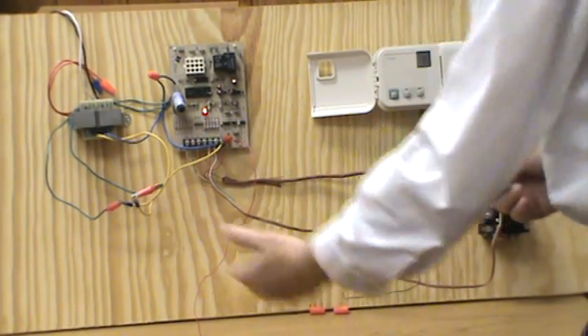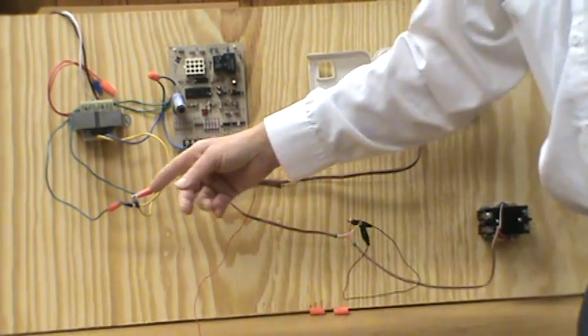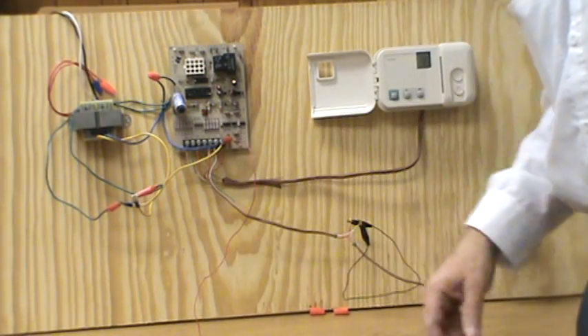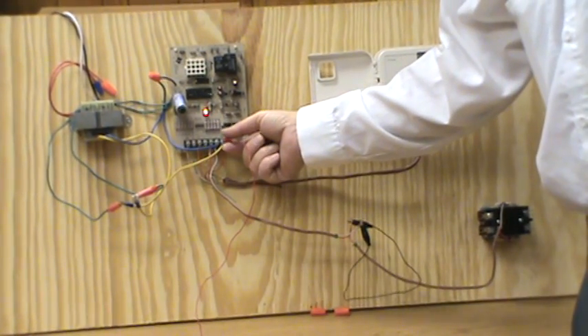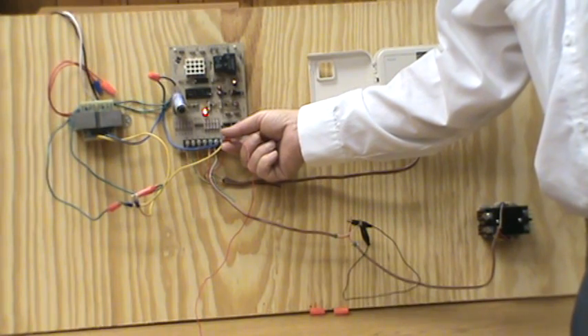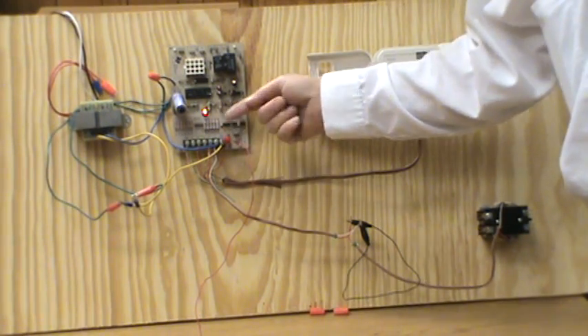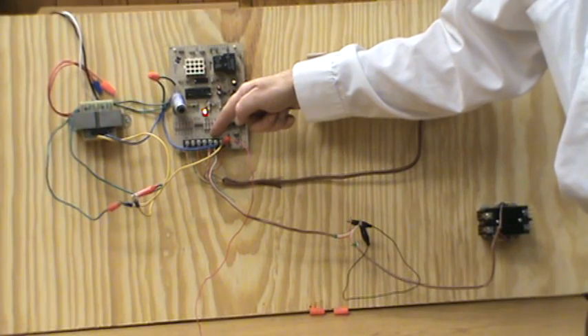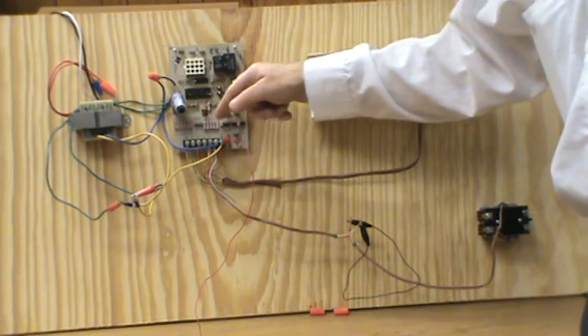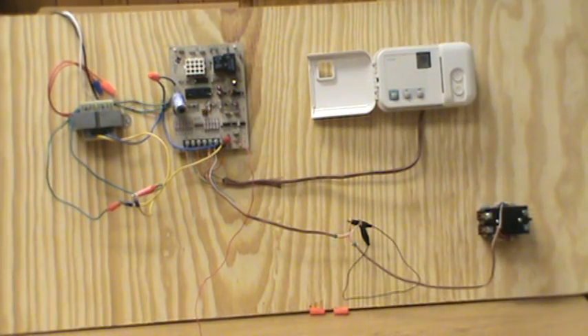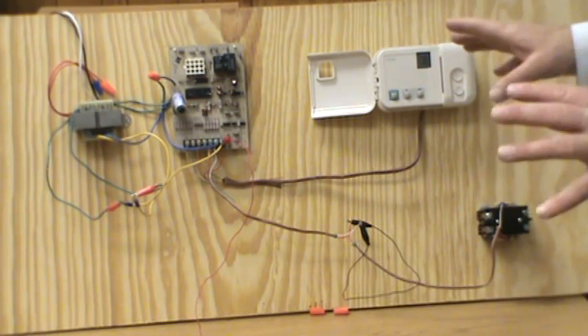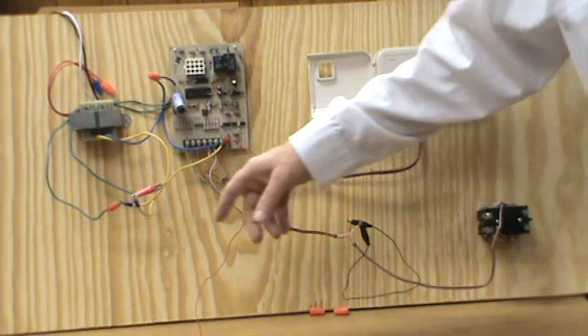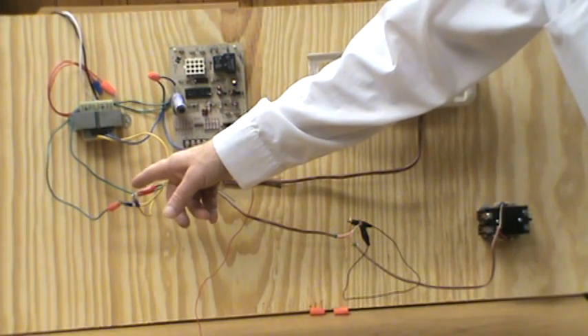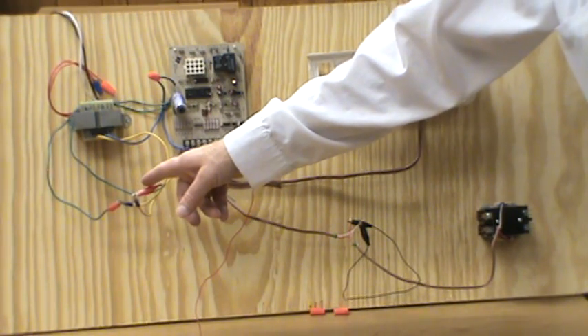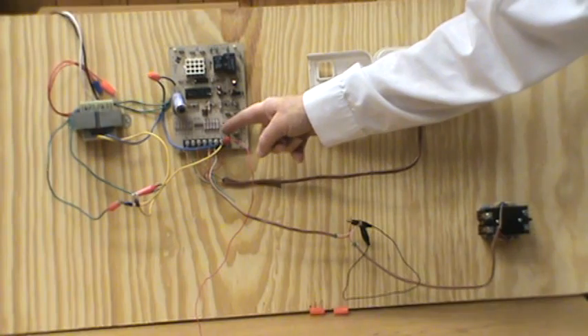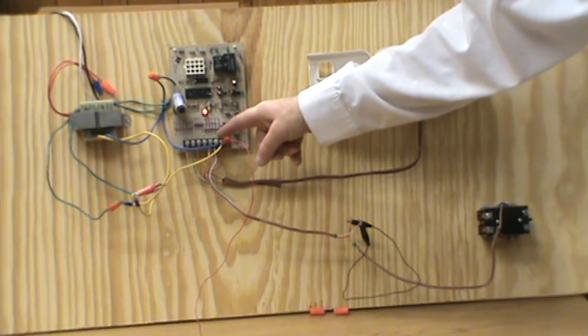That's what I've done here, is I've got it clipped across where the blown fuse was, and then we're going to use a red clip on the red load side. And what we're going to do is eventually hit each branch circuit to find out which one has got the high current. And so the first part of the instructions say, do this, cut off the power, take the blown fuse out, clip your Short Pro tool across where the fuse was, and let's get this red jumper lead attached.